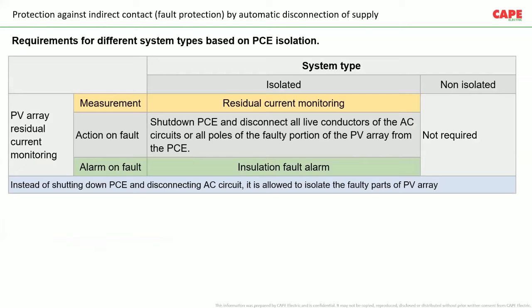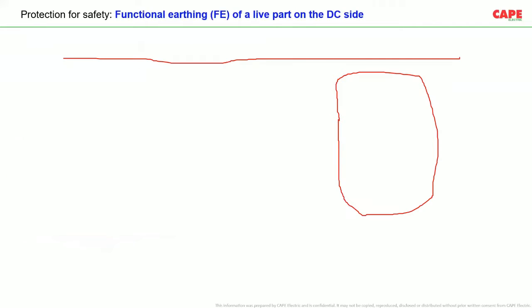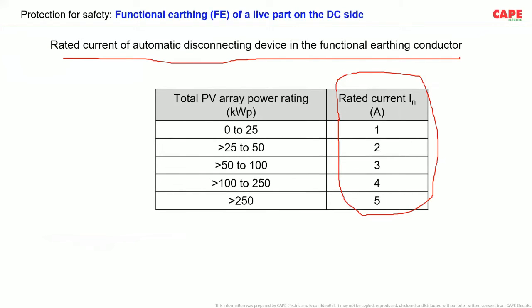The next method is residual current monitoring. Residual current monitoring is where the current flowing through the functional earthing system is monitored, and the functional earthing is disconnected in order to achieve safety. So these are some of the techniques which are used for fire protection in solar PV.